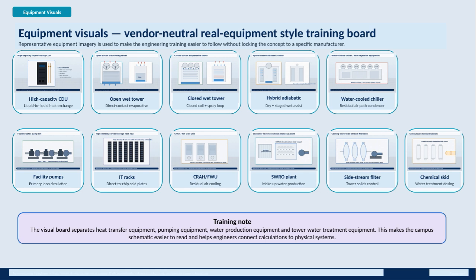On the water production side, we feature the SWRO plant for makeup water production, side stream filters for tower solids control, and chemical dosing skids for water treatment. The key takeaway here is that the visual board distinctly separates heat transfer equipment, pumping equipment, water production units, and tower water treatment components. This organization makes the overall campus schematic more readable and helps engineers more effectively link their calculations to the actual physical systems they work with.